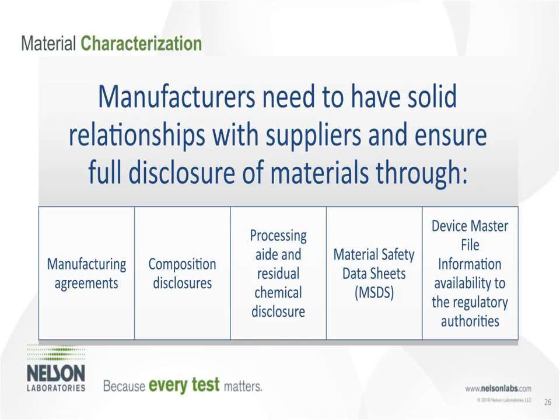One of the best things to get is a device master file. This is something that they submit to the FDA to basically get a pass themselves from the FDA. Now, like I mentioned before, the new guidance document has a whole section on what a master file should entail. So don't think that a master file is just a pass to go. It is very useful, but any master file should include what that new guidance document has in it as far as what is recommended by the FDA. And then also remember that that master file is just for that material. It's not for what you're doing to it. So you still have to address the processing, but the master file is very helpful.